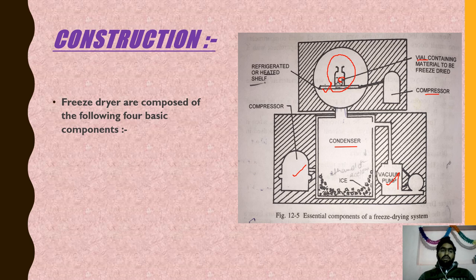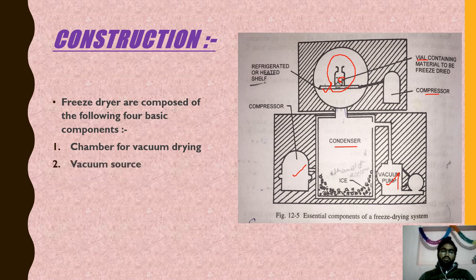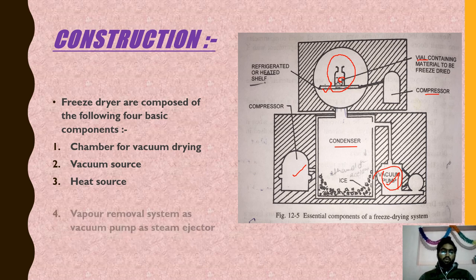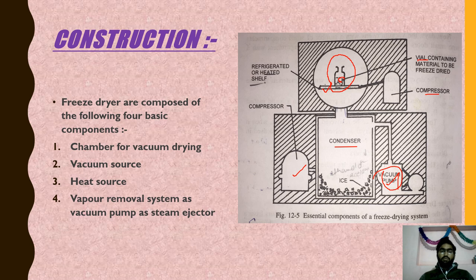Freeze dryers are composed of four basic components: first, a chamber for vacuum drying; second, a vacuum source (vacuum pump); third, a heat source placed beneath the bottles or vials; and fourth, a vapor removal system such as a vacuum pump or steam ejector.